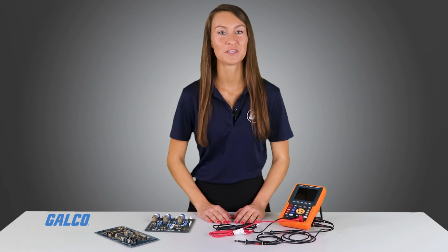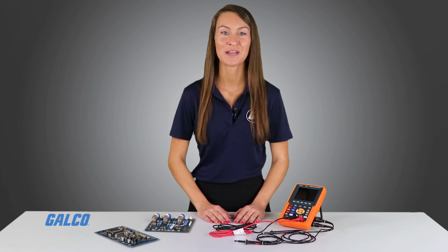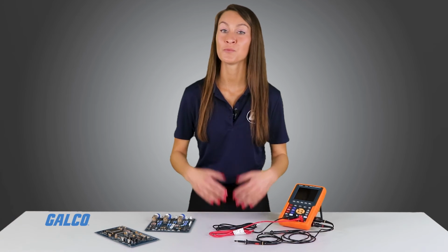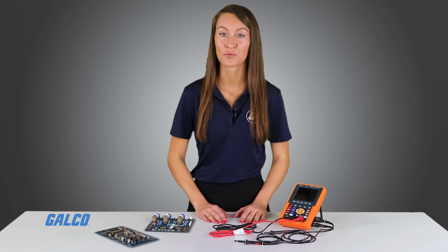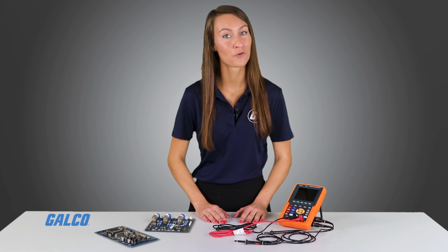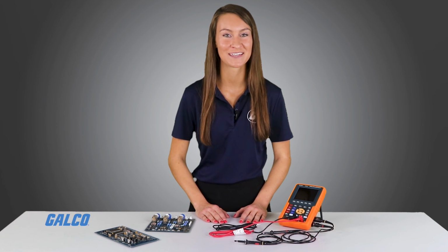You should also keep the channel toggle buttons in mind if you do not see a waveform displayed when you may otherwise expect one. In some cases, you may have just toggled off the appropriate input, so always double-check that when troubleshooting before moving on to further troubleshooting methods.